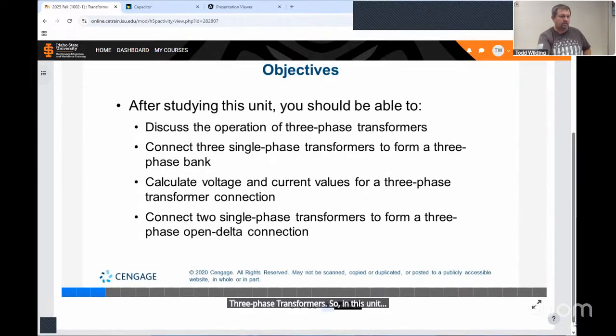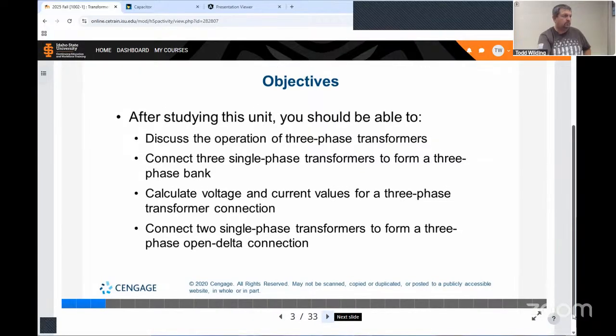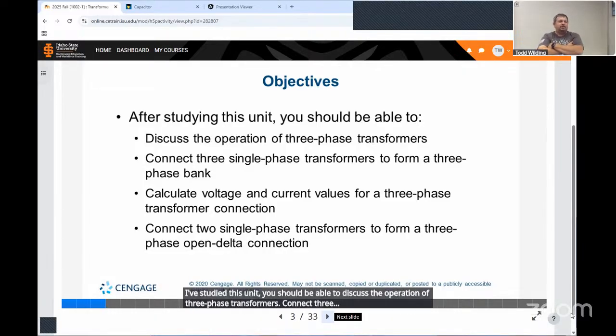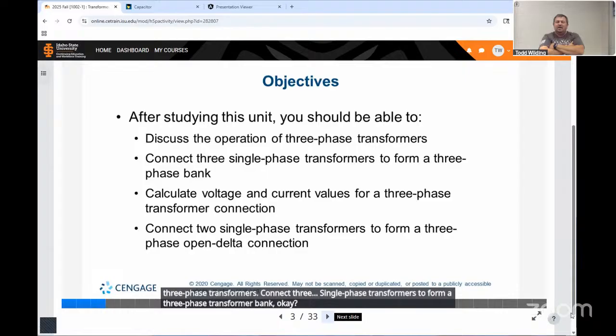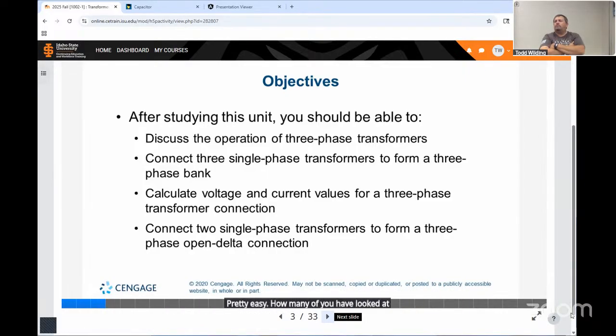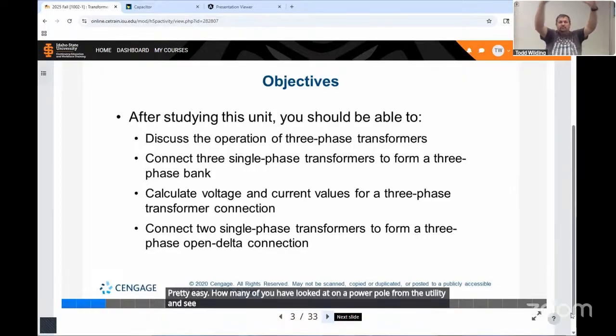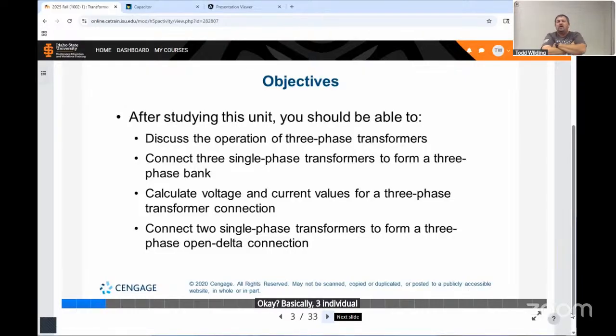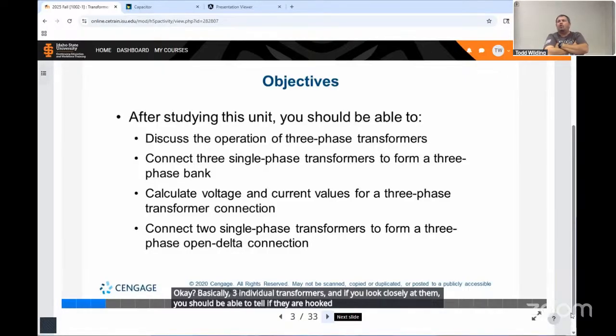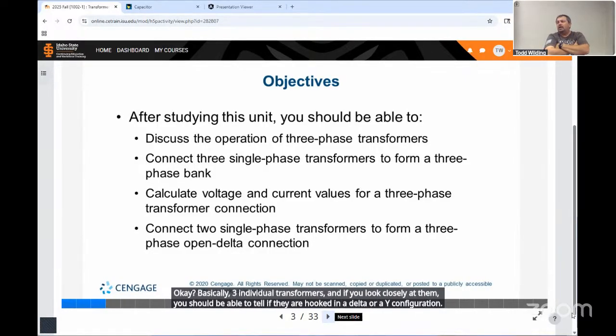Three-phase transformers. So in this unit, after studying this unit, you should be able to discuss the operation of three-phase transformers. Connect three single-phase transformers to form a three-phase transformer bank. Okay, pretty easy. How many of you have looked out on a power pole from the utility and seen three individual transformer buckets? Okay, basically three individual transformers. And if you look closely at them, you should be able to tell if they are hooked in a delta or a Y configuration. Okay.